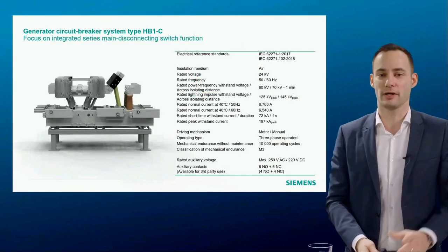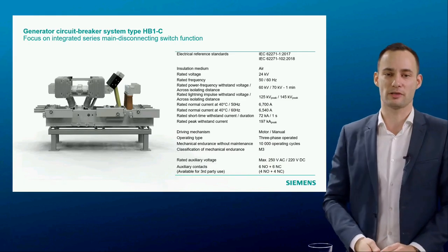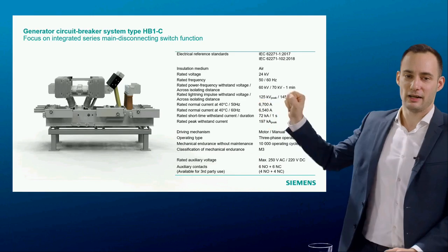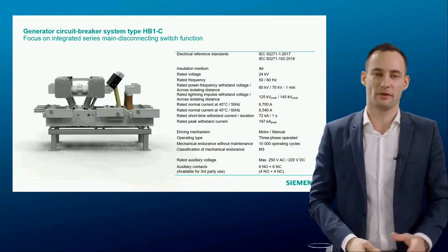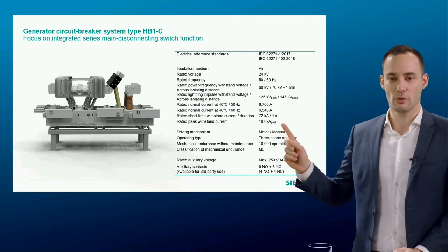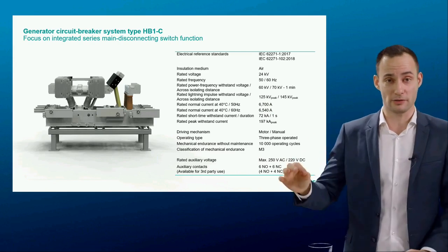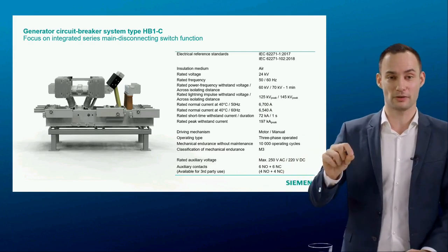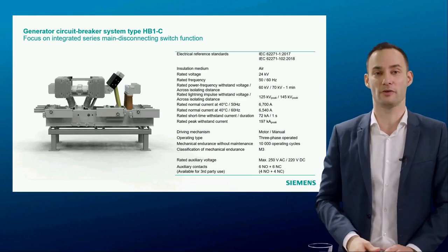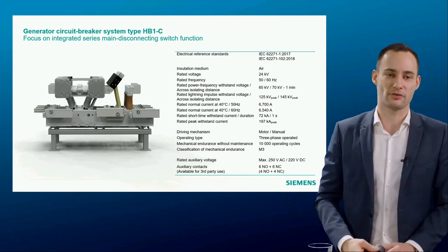Now, quickly going through the disconnector. As you can see here, I bring some data about the disconnectors. What you can see, which is quite important, is this insulating distance. So the rated voltage and rated power withstand voltage across the insulating distance. Again, as we were doing and initiating our own type test, we were able to fine tune and to select properly the disconnectors so they fulfill the requirement of the dual logo standard. That was very important for us. And again, here you can see the M3 durability class or endurance class on the disconnectors.